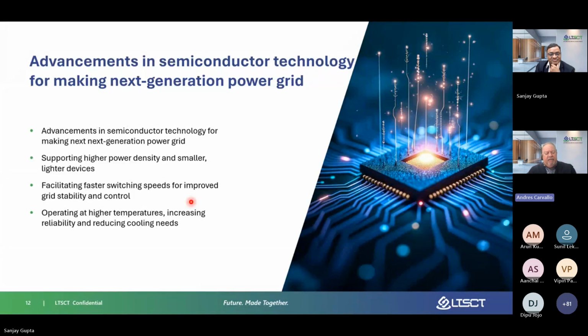So think about that for a moment. If the budget to make energy is one billion dollars, you only get 500 million of delivered energy at the edge of the grid. By switching to solid state components, putting semiconductors everywhere and eliminating magnetics and electromechanical infrastructure, you gain a tremendous amount of efficiency. You reduce the losses of the grid, and you also allow for control of the modulation, harmonics, and power quality that is disrupting many stakeholders who now want better power quality.